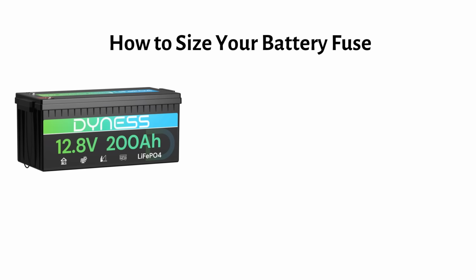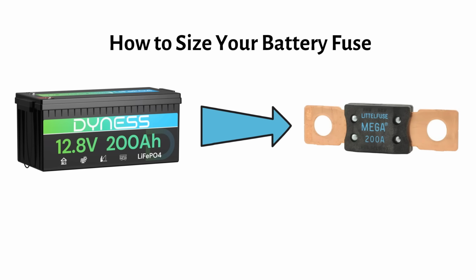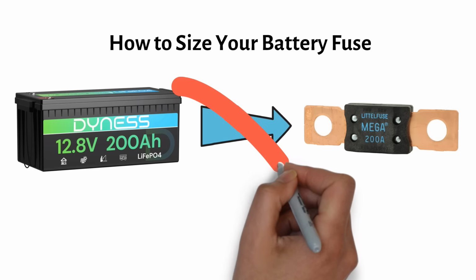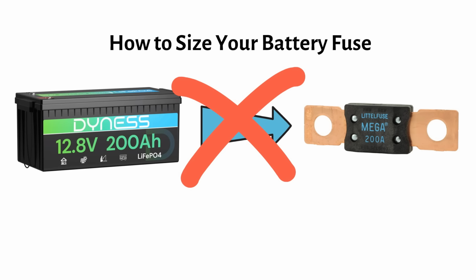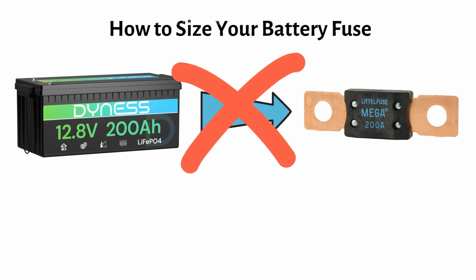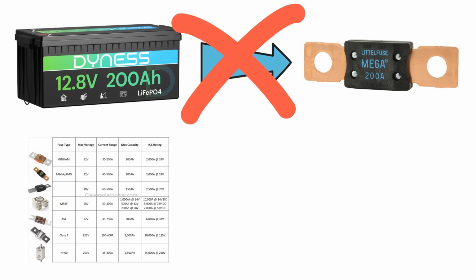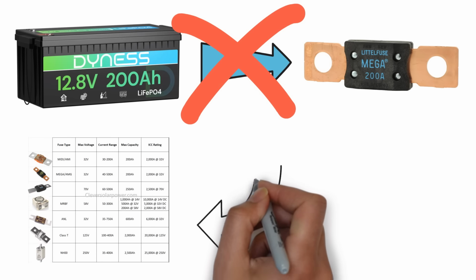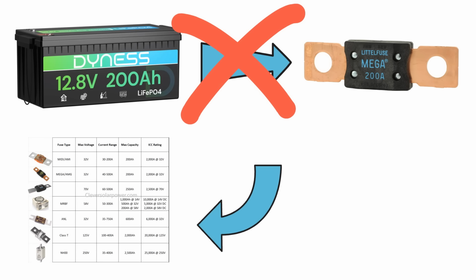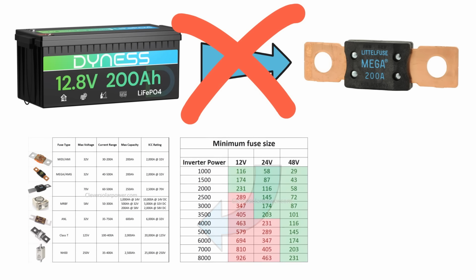Some people say if you have a 200 amp hour battery, you need a 200 amp fuse. But that's completely wrong. In this video, I'm going to show you the right way to size your battery fuse. I will show you which fuse types are safe to use on 12, 24 and 48 volt batteries using my custom chart. I also give you my recommended fuse sizes for your inverter at different voltages.